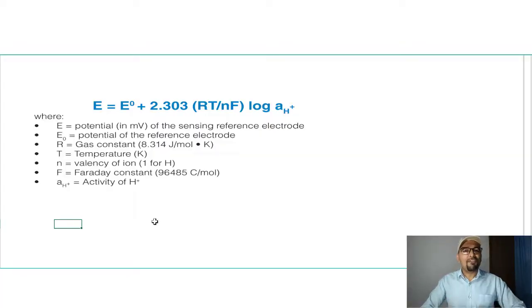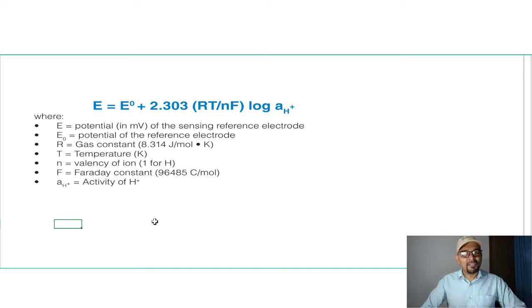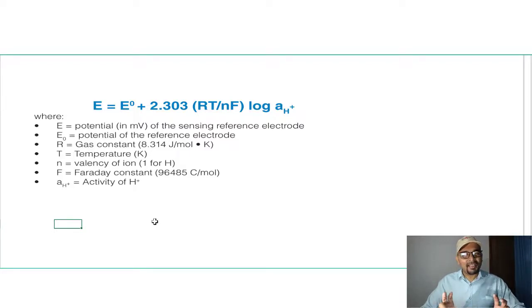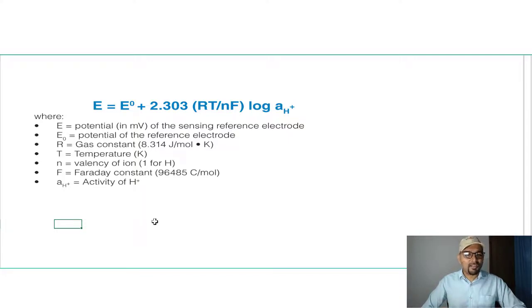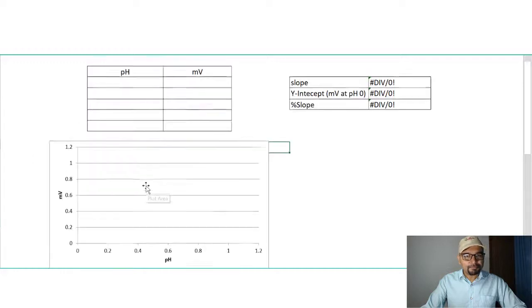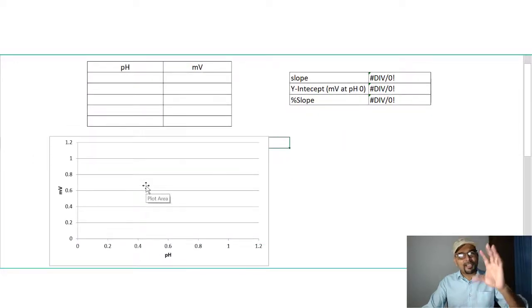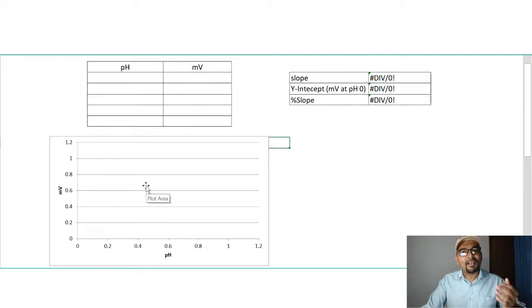The pH value is calculated using the Nernst equation, as you can see on the screen. This is the way pH value can be calculated using a suitable pH electrode. I am now going to explain how the slope and offset values during calibration of the pH meter can be calculated.